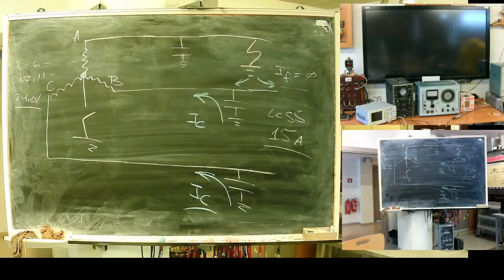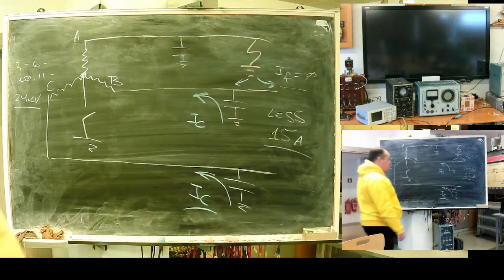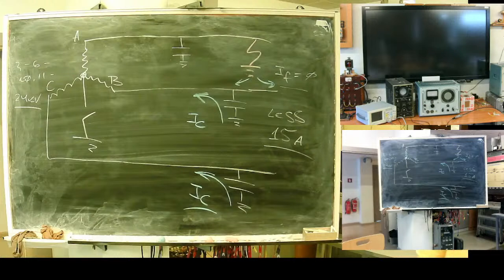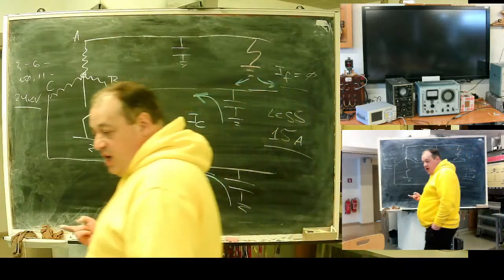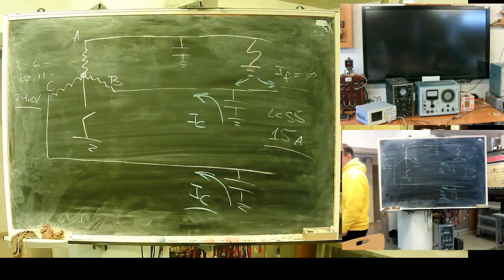What's the work current for this distribution line? 1,000, 2,000 amps, yeah? And fault current, 10, 15, 20, maybe 50 amps. We have a problem with sensitivity. Fault current is very small. These isolated neutral networks, this type of network, was implemented because of small fault current. Because most of the faults are earth faults and the current will be small, the network can remain operational for a long time.